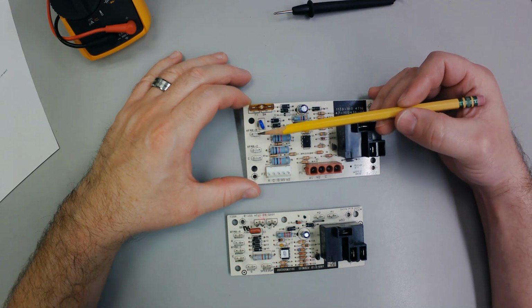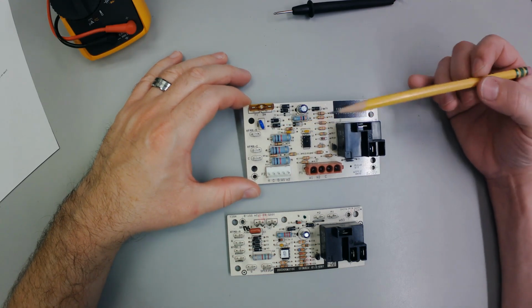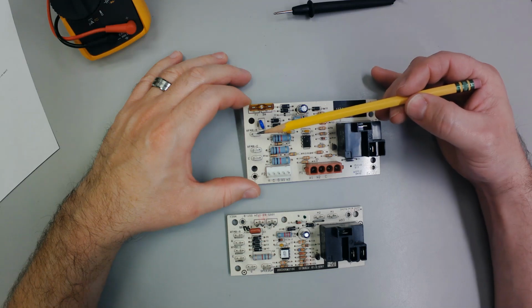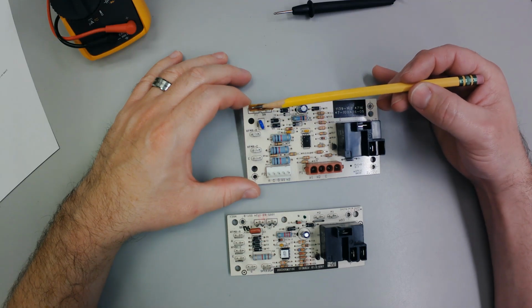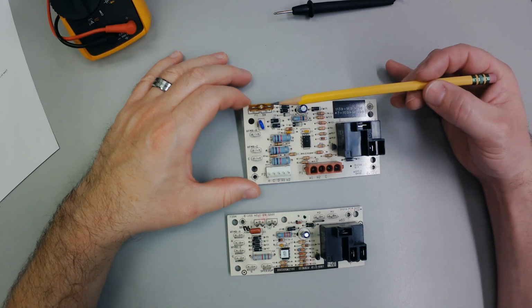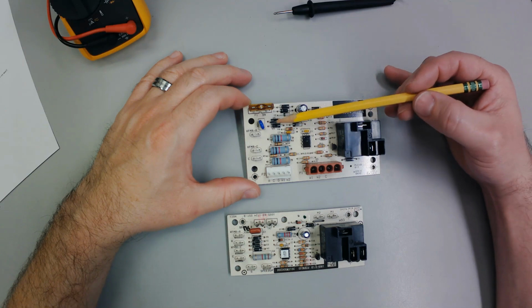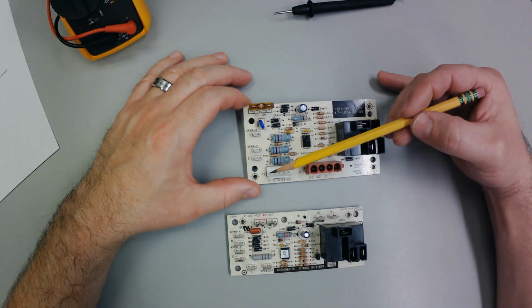Transformer R, this is where power comes in. This is the one red wire coming from the 24-volt transformer. It goes in here. And what it's going to do is feed into this 5 amp fuse or 3 amp fuse. If the fuse is good, it passes power across, and then that circuit within the board is going to go straight over here to this R.